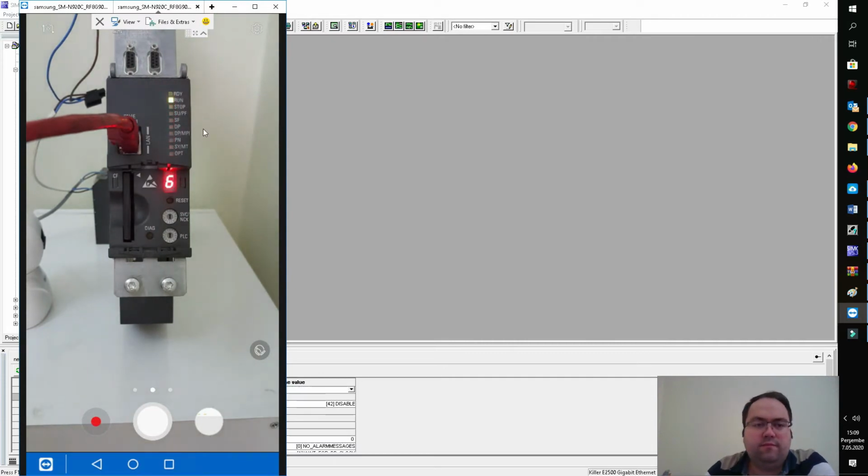You see the stop and SU LEDs are blinking orange, at about a 2 Hz frequency. After creating the diagnostic files on your CF card has finished, you see the LEDs light off again and your run LED is green standstill again.